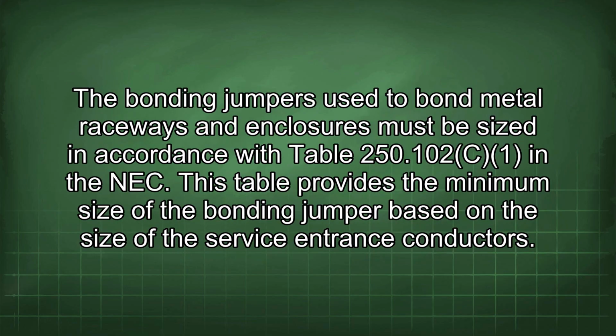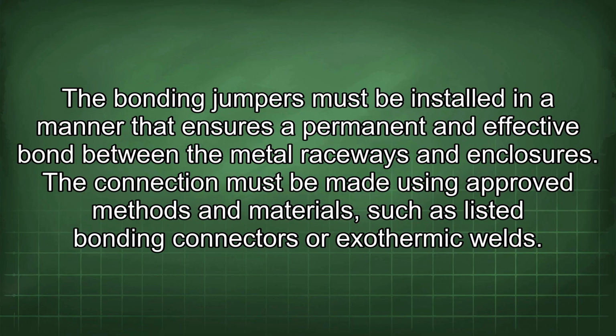The bonding jumpers used to bond metal raceways and enclosures must be sized in accordance with Table 250.102 in the NEC. This table provides the minimum size of the bonding jumper based on the size of the service entrance conductors. The bonding jumpers must be installed in a manner that ensures a permanent and effective bond between the metal raceways and enclosures. The connection must be made using approved methods and materials such as listed bonding connectors or exothermic welds.